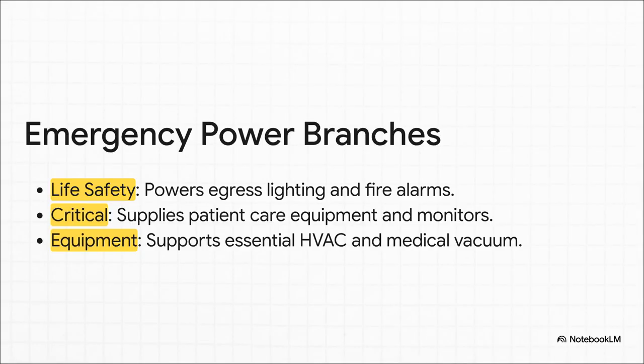Not all emergency power is treated equally. The system is split into 3 different branches, prioritized by importance. The life safety branch powers things like fire alarms and exit lights. The critical branch is for patient monitors and life support machines. And the equipment branch runs essential machinery, like medical vacuum pumps and crucial ventilation systems.